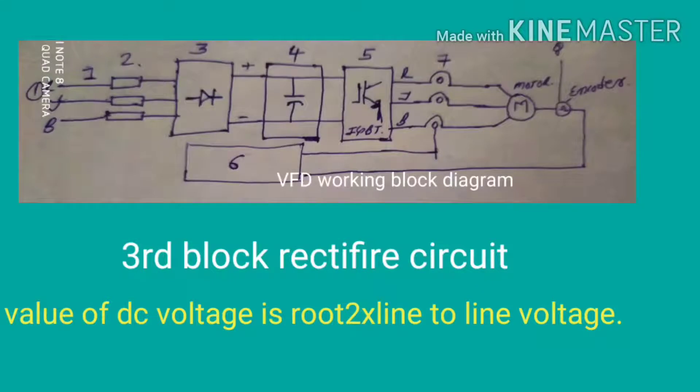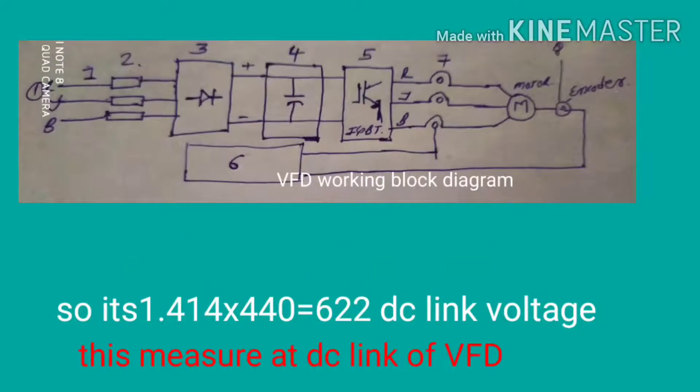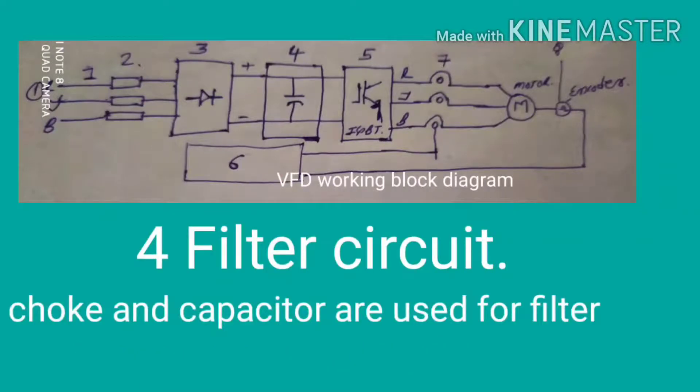The value of this DC voltage is root 2 into line to line voltage, so it's 1.414 into 440 equals 622 DC link voltage. This DC link voltage is also available on the VFD and we can measure this DC link on the VFD.